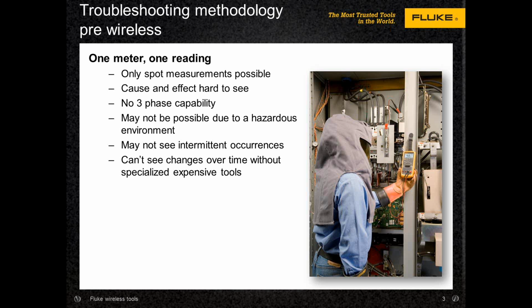Also, if you're making three-phase voltage or current measurements, you have to make one measurement at a time unless you have a three-phase analyzer, and those things typically start at $3,000 or $4,000 and go up from there. And of course, if it's three-phase, every time you change the measurement location, you have to don all your PPE gear. Right. The other thing is with conventional tools today, especially around hazardous environments where you're working around moving machinery or robotics, or a conveyor system, you can't be next to whatever it is you want to see, so the wireless capabilities help alleviate some of those situations.